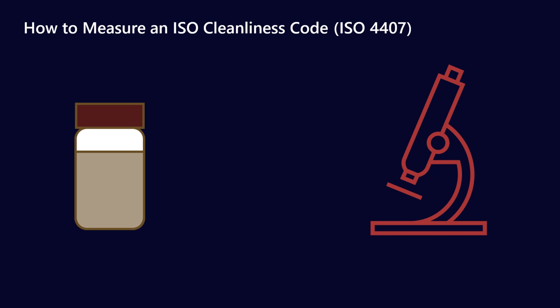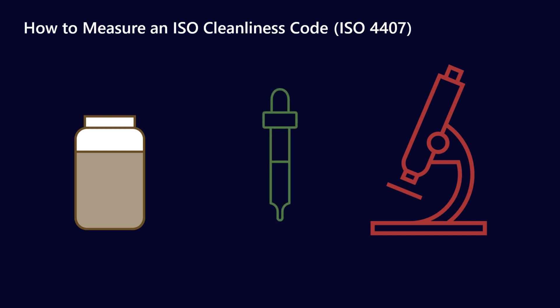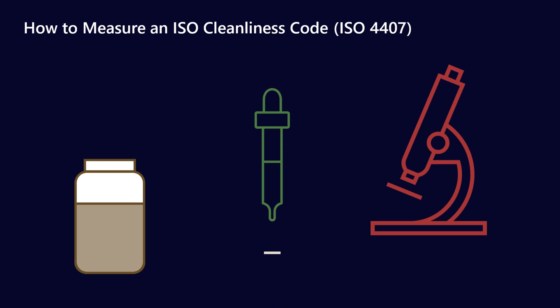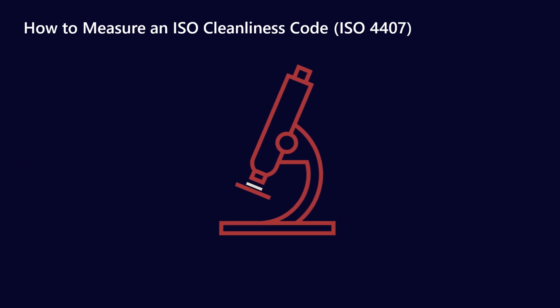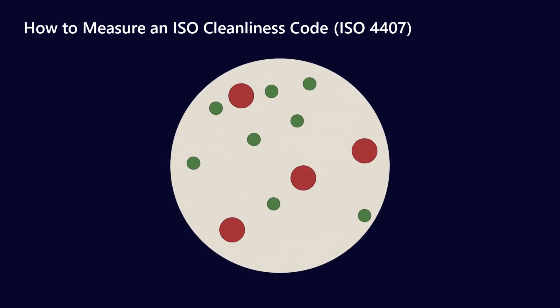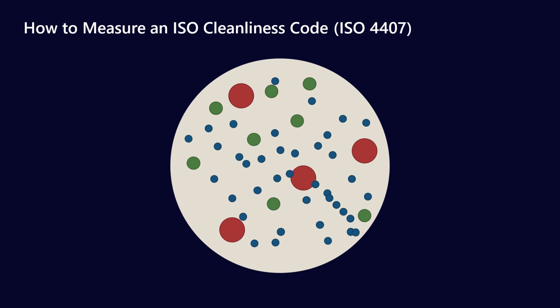So how this method works: you have a used oil sample, and what the lab does is take a little bit of it — probably with an automated machine rather than an actual pipette — and pass it through a filter patch. This filter patch is then looked at under a microscope, where you'll see a whole bunch of different particles of different shapes and sizes. To simplify for this presentation, we have three different sizes of particles roughly in the 4, 6, and 14 micron range.